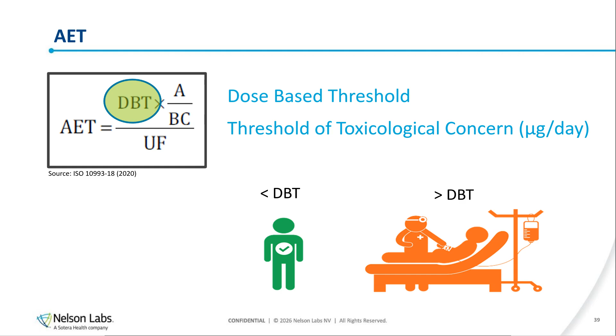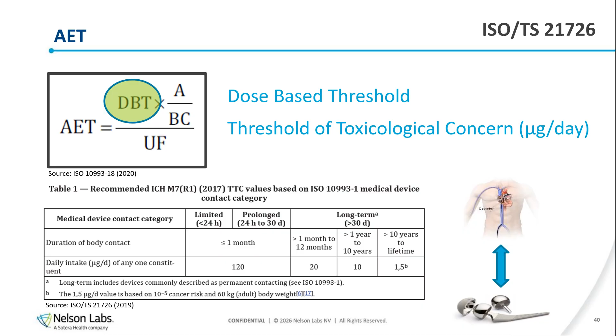So first we see for the AET calculation, you need a DBT or a dose-based threshold, which is the same as a threshold of toxicological concern, the TTC. And this TTC can be found in ISO TS 21726. There's a table in there that will specify the TTC that you can use based on the patient contact duration. So you can see it here in the table below. And just as an example, if you have a very long-term, so over 10 years implant, like the example here, we see a hip implant, it's most likely going to be used over 10 years, then you need to use a TTC or a DBT of 1.5 micrograms per day. But if it's a very short contact, then you can use 120 micrograms per day.